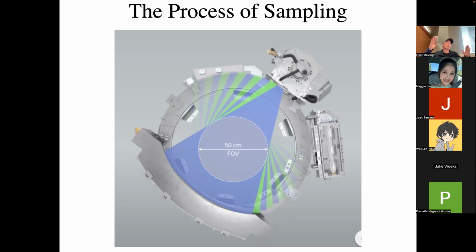So you have to have them big enough that you get enough photons to get a reasonable measurement. Secondly, in the current CT detectors, there's a flash of light which needs to be contained inside the box. To contain it, you need some septa that reflect the light back and forth, so you lose efficiency. So as you put more and more samples, the ratio of area that's sampling versus septa goes down, and your efficiency goes down.